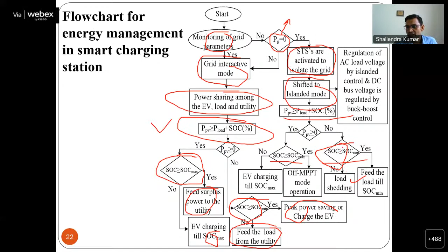However, in standalone mode, again we check the PV power and the SOCs. If SOC is less than SOC minimum, then we will operate in load shedding. Here you can see, if SOC is not greater than SOC minimum, we have to provide load shedding, because PV power is not there, the grid is not there, and the SOC of the battery is also hitting the lower limit. So we don't have any source within the charging station, and we cannot supply power to the onboard charger or loads connected with the charging station. So we need to do load shedding. Only emergency load we can switch on and the rest of the load can be shut down. And if SOC is greater than the SOC limit, yes, we can feed the power till SOC minimum.